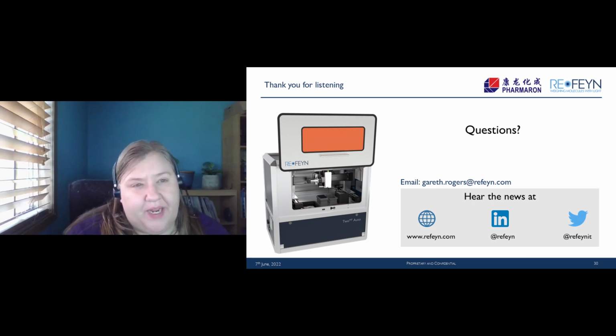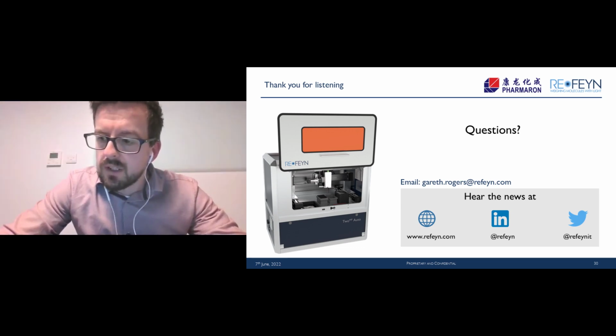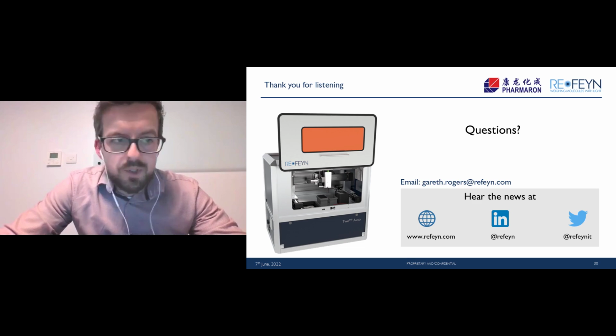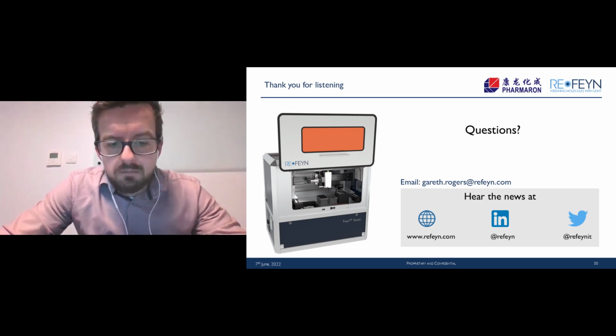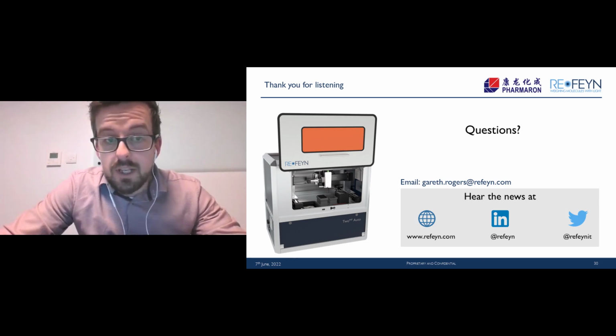What is the minimum AAV sample concentration you can use with the SAMX? So where sample concentration is concerned, in order to generate the best results, we would typically recommend working with a sample concentration of 10^11 particles per mL. But you can certainly work with samples that have a particle concentration of 10^10 particles per mL.